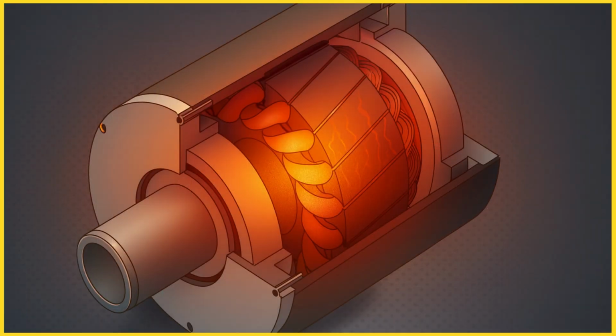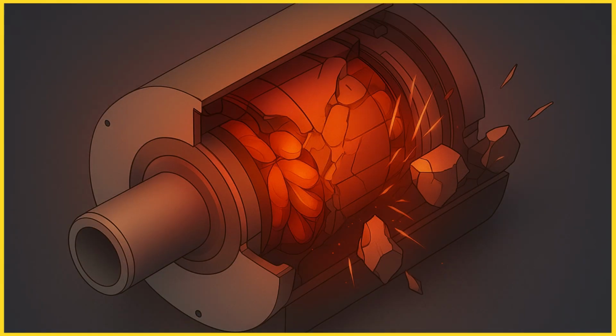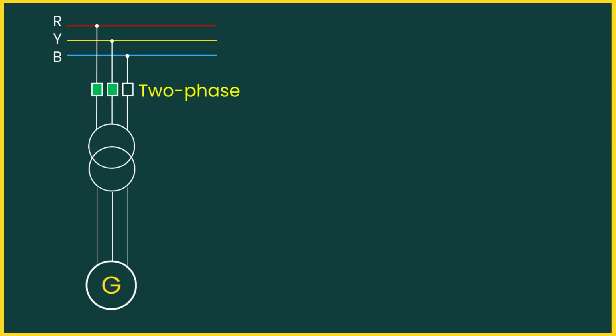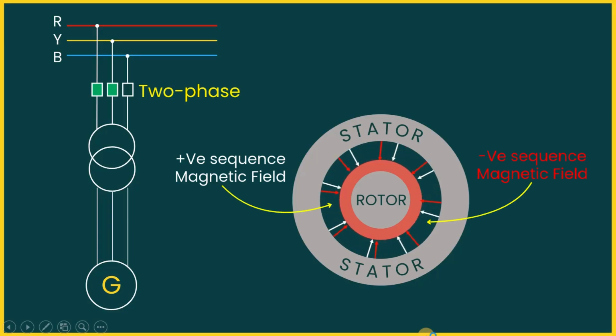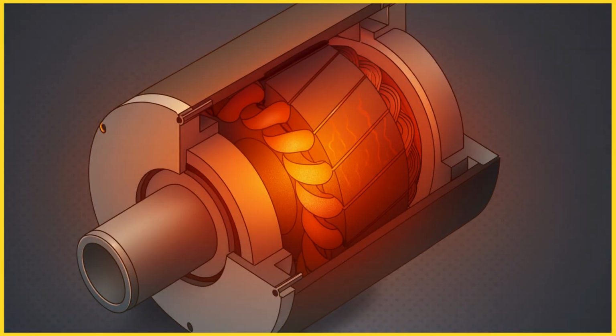The stator, on the other hand, can usually withstand the short-duration current. But if rotor heating continues, rotor parts may break off, strike the stator, and cause serious mechanical damage, sometimes even total generator failure. If only one phase or two phases are energized, severe unbalanced currents flow, producing strong negative sequence components. These currents in the stator induce strong eddy currents in the rotor body, causing intense heating. This single or two-phase energization, often caused by open breaker flashovers, can damage the rotor within seconds. So clearly, the effects are severe.